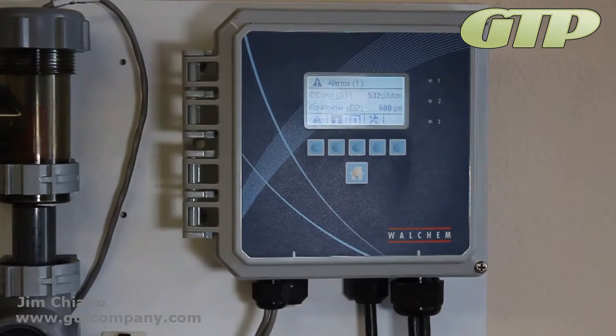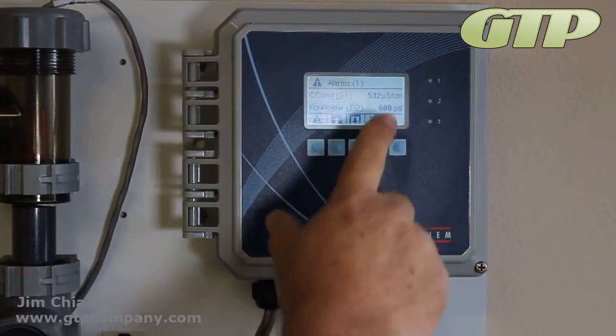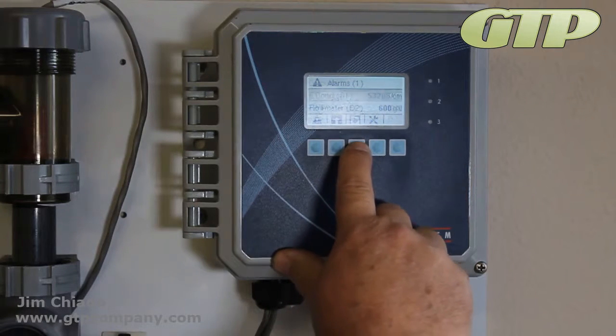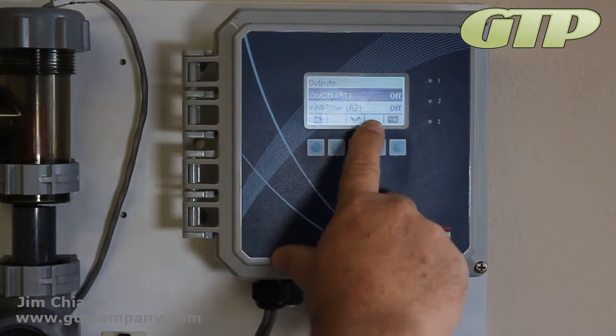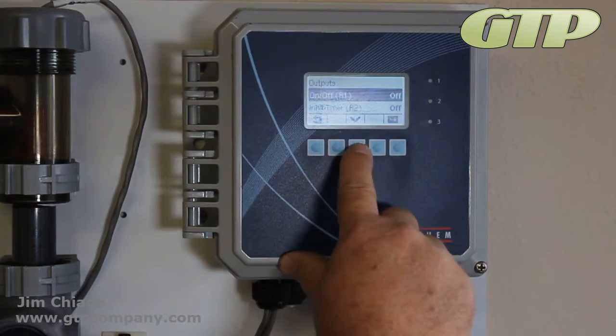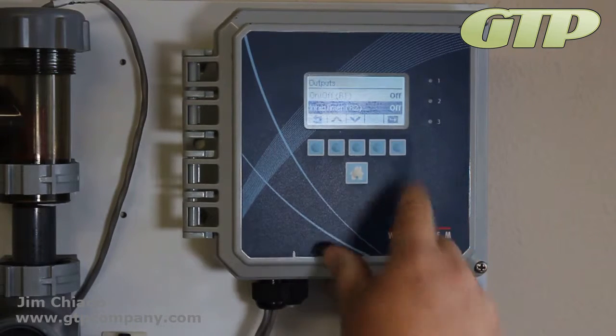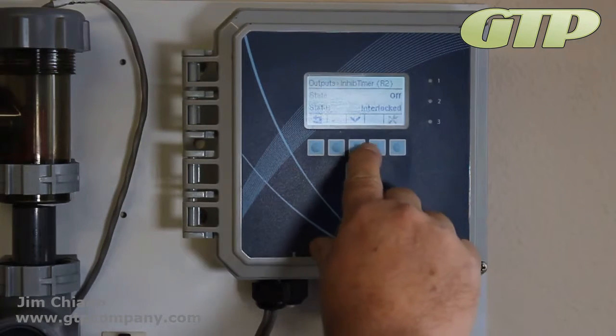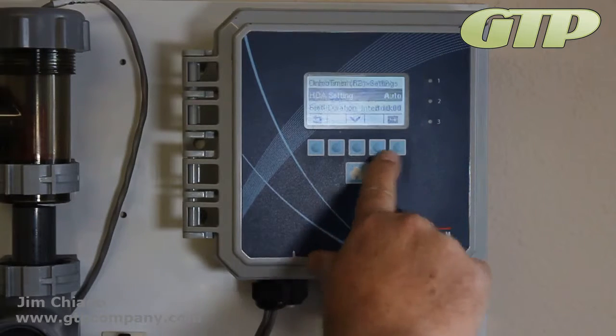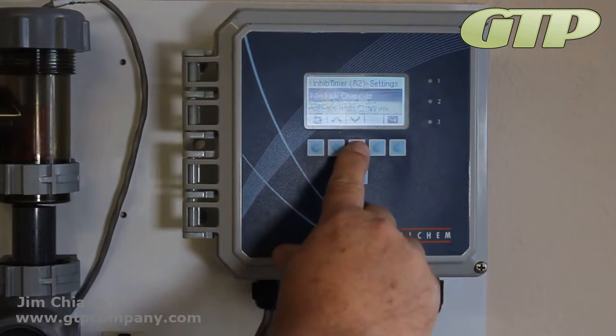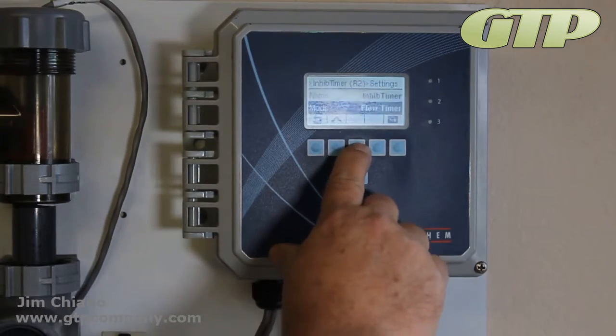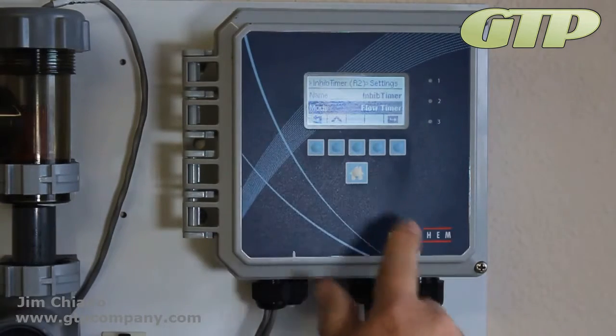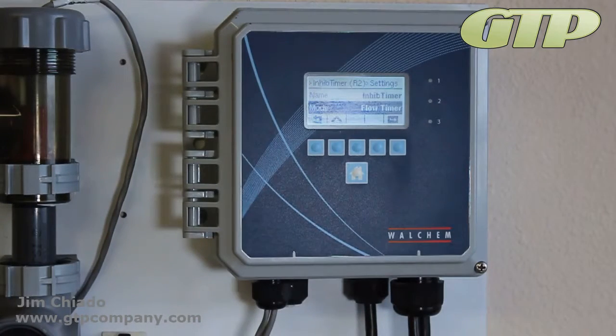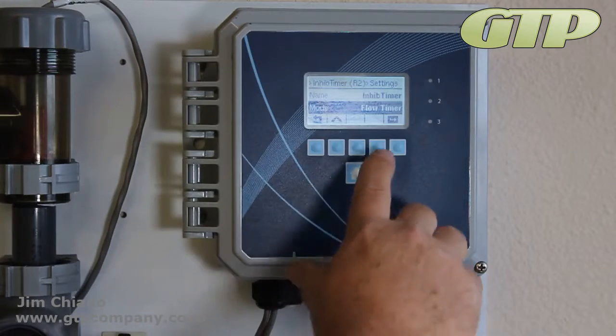This session, we'd like to show you how to set a relay based on a flow meter feed. So what we're going to do is go into outputs, go down to R2, which is the one that we want to set for our inhibitor feed. So do the maintenance, and what I want you guys to always do on these things is go to mode. Mode is the way that the relay reacts, and if you're in the wrong mode, might as well forget about what programming you're doing there.